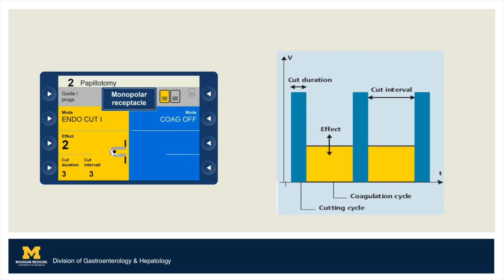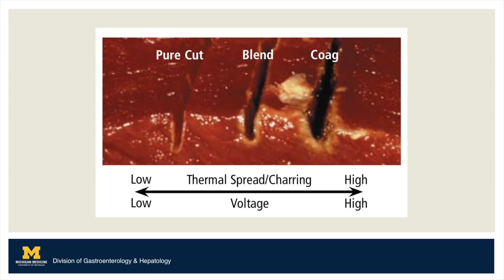As shown on the graph on the right, adjustments in the duration dictate the length at which the cutting portion of the current is applied. Adjustments in the interval will change the time between the application of each cut. Adjusting the effect will change the amount of tissue coagulation performed by the device, with higher effects leading to more coagulation. Notably, in order to obtain the coagulation effect of this blended current, the pedal needs to be stepped on continuously instead of intermittently.